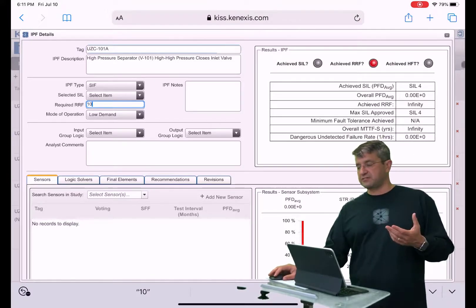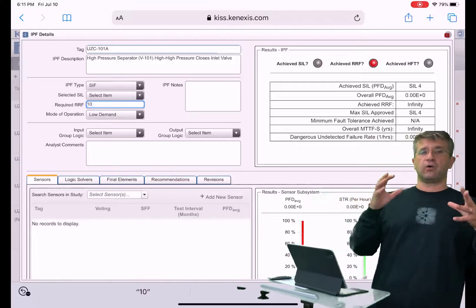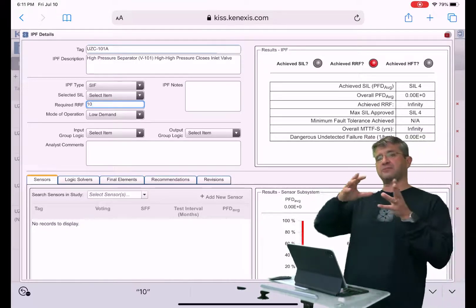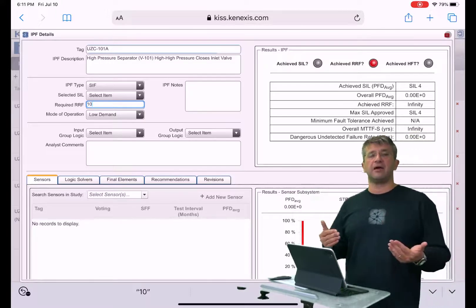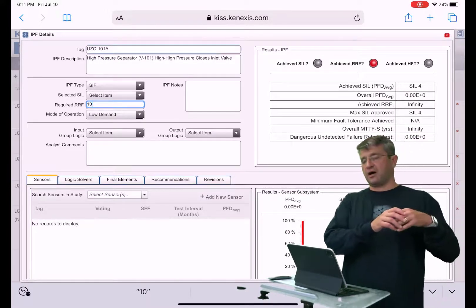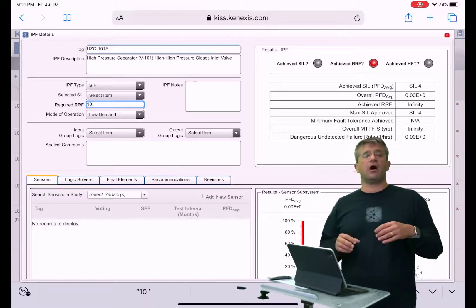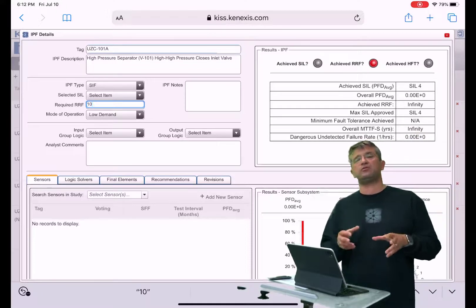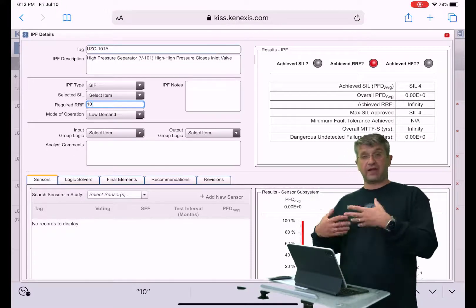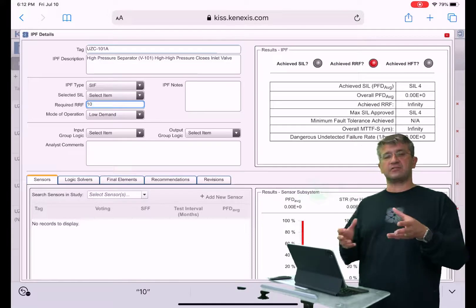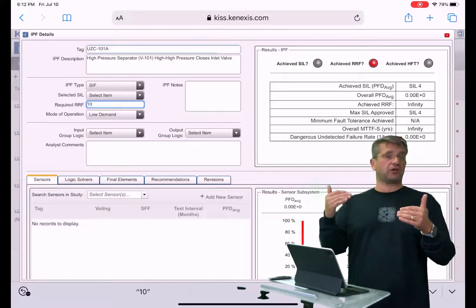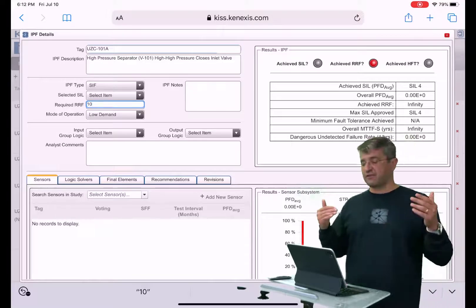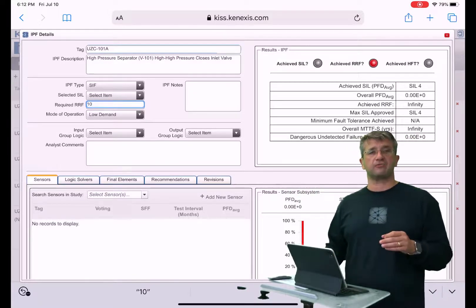So it's the starting point that allows you to keep your LOPAs, your HAZOPs, and your SIS designs automatically synchronized. Because whenever you make a change in your HAZOP LOPA—whether it's a change of a target or adding new functions, deleting functions—when you do that you can either create a new study if it's a new project, or you can synchronize to make the two studies match up with each other. A very powerful feature of the premium version of the software.